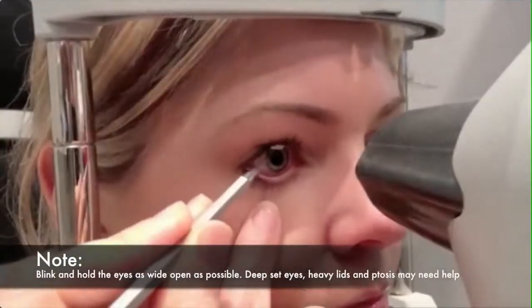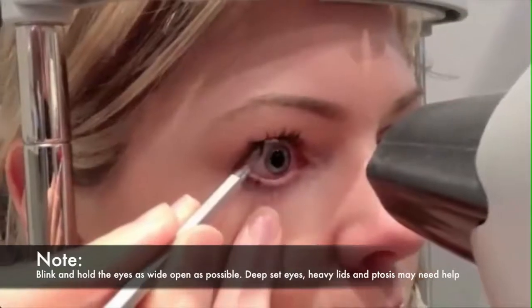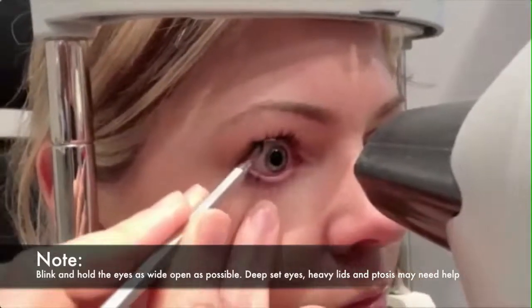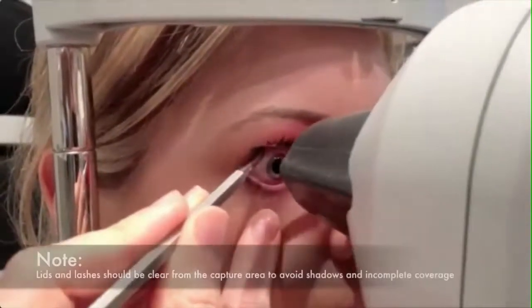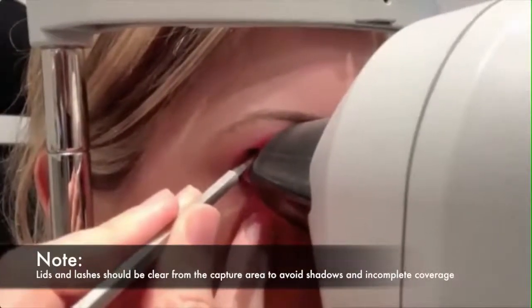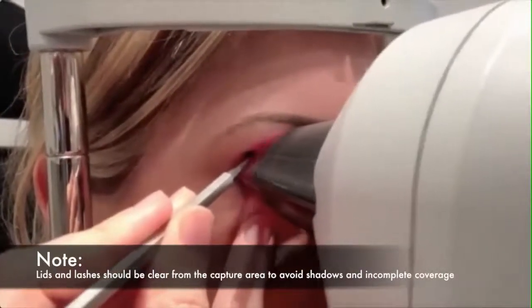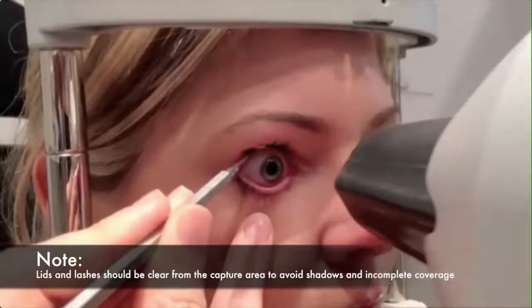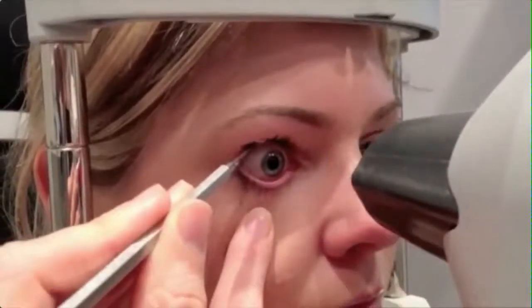It is also important to note that when the cone comes close to the cornea, the lid should be completely out of the way to avoid decreased capture area and shadows of the Placido mires. A cotton bud, lid retractor, or finger manipulation of the lid can aid this.